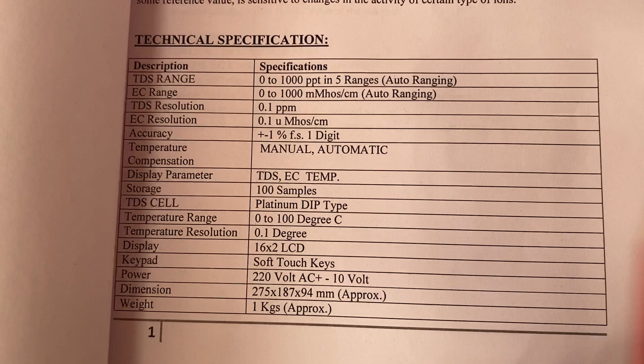It can store 100 TDS and EC samples. The temperature sensor is a platinum dip type with a range up to 100 degrees centigrade and 0.1 degree accuracy. It has a 16 into 2 line display, soft touch keys, and a 220 volt power supply, and then there is a TDS conductivity cell. It is a combined cell, with stand and manual.